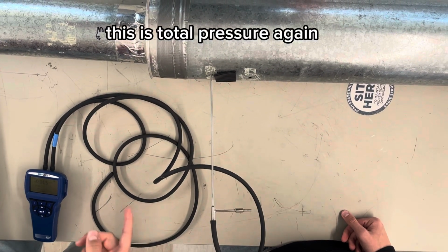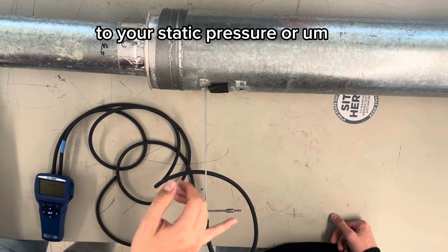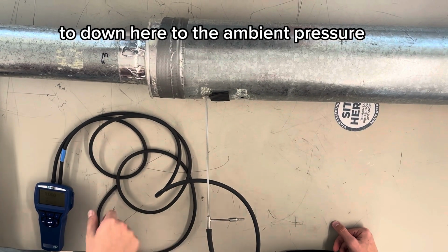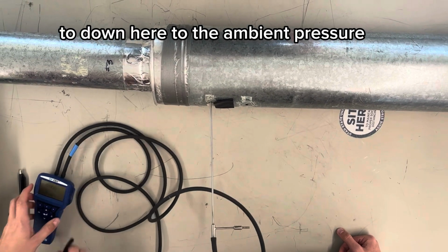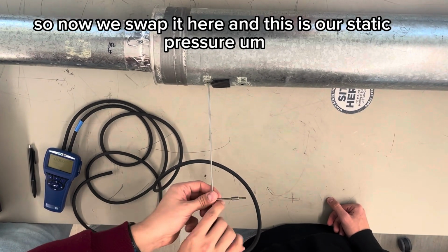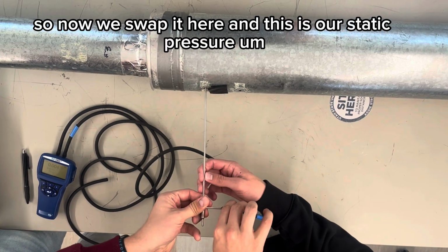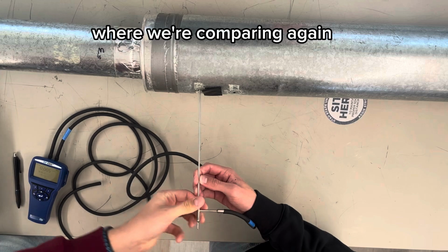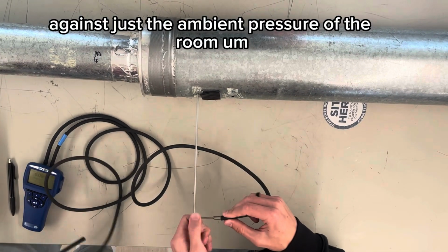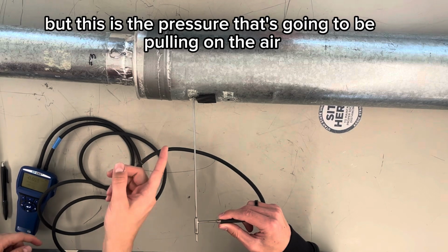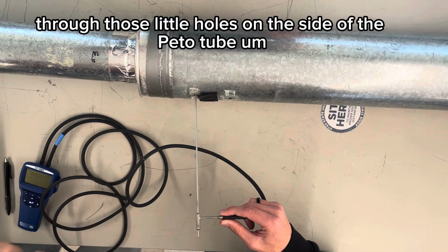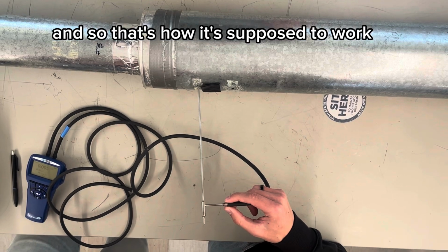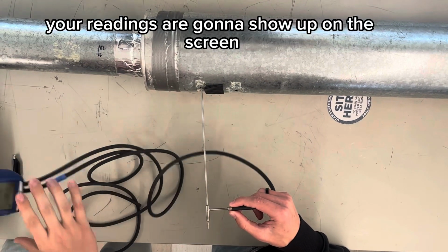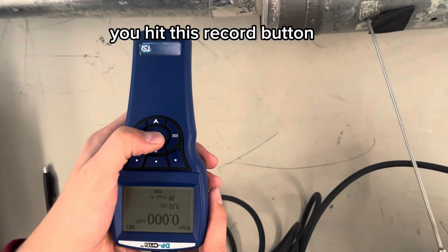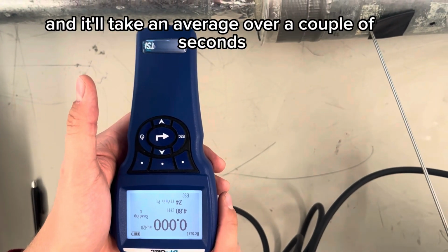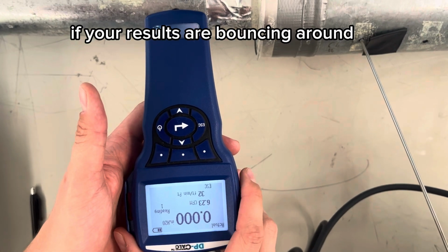This is total pressure. Again, you're comparing the flow coming directly downstream to the ambient pressure. Now we swap it here, and this is our static pressure, where we're comparing again against just the ambient pressure of the room. But this is the pressure that's going to be pulling on the air through those little holes in the side of the pitot tube. And that's how it's supposed to work. Your readings are going to show up on the screen. If you want to take an average, you hit this record button. It'll take an average over a couple of seconds if your results are bouncing around.